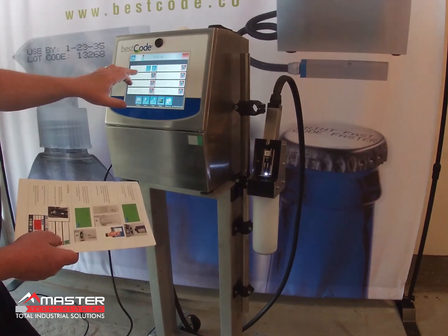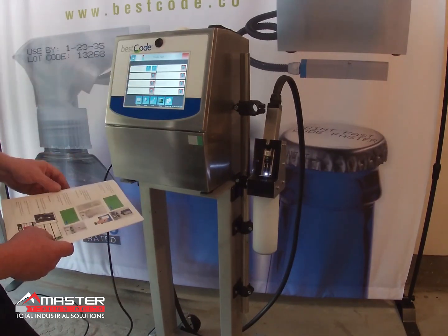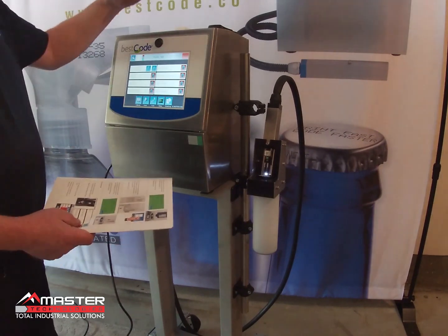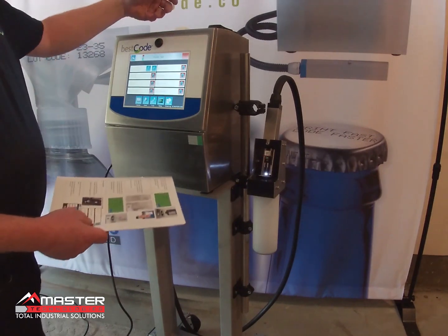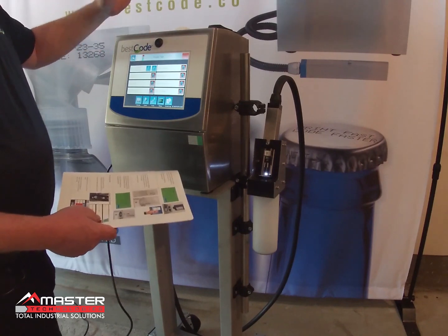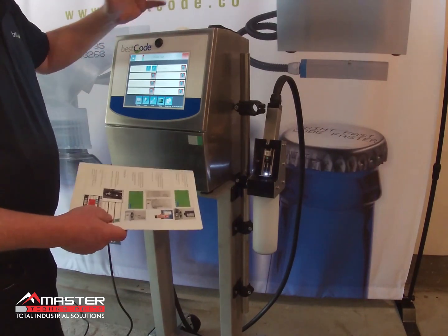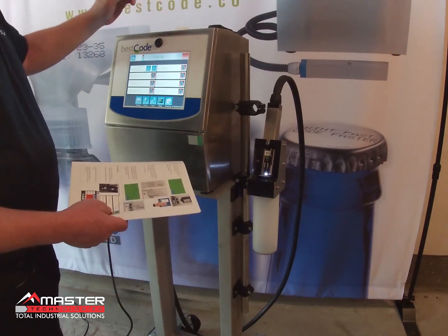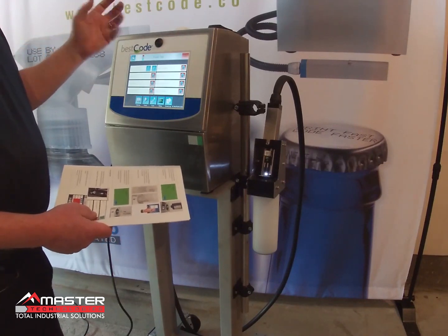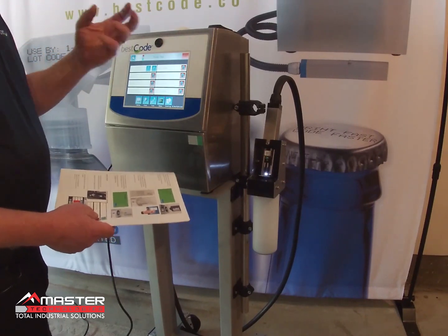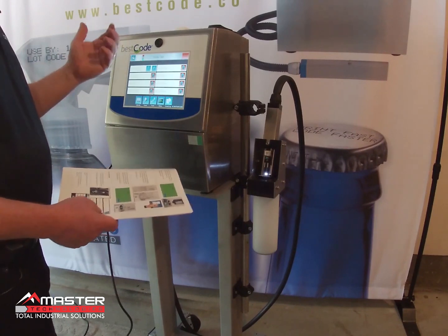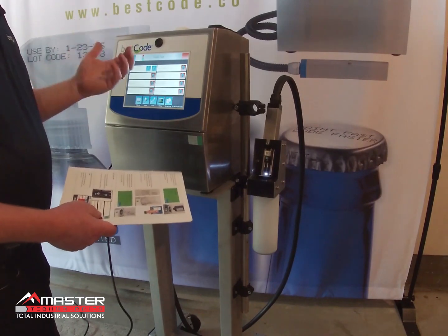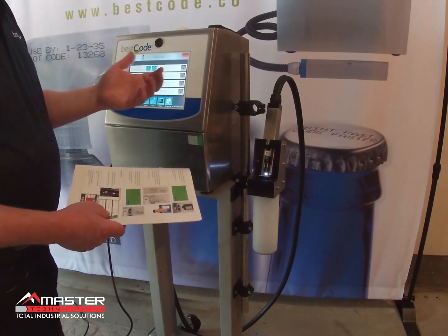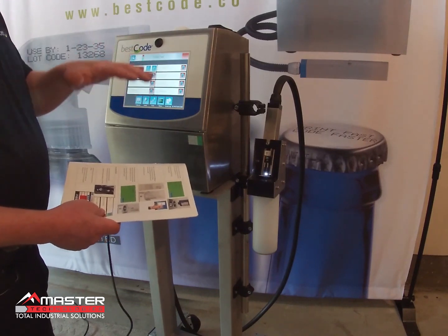You can see we're now at 7 RPS, 4 PSI. What this is going to do is slowly put ink in the system, fill up the filter, that 10,000 hour filter, or whichever filter module you have in there, and pull ink from the tank. It would load it through, going through all of the different parts, like the Venturi and the viscometer, but it will slowly fill this up.